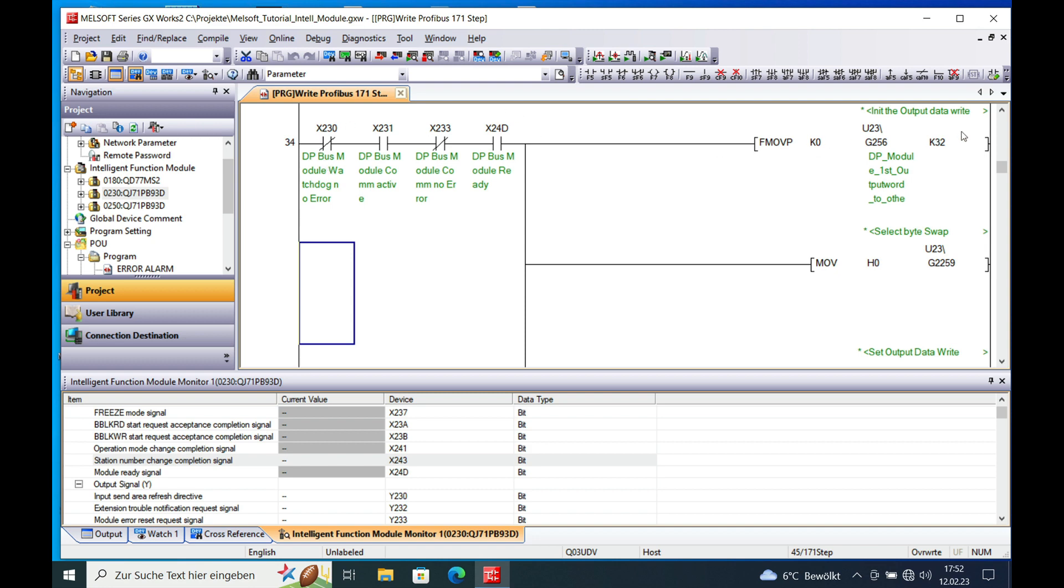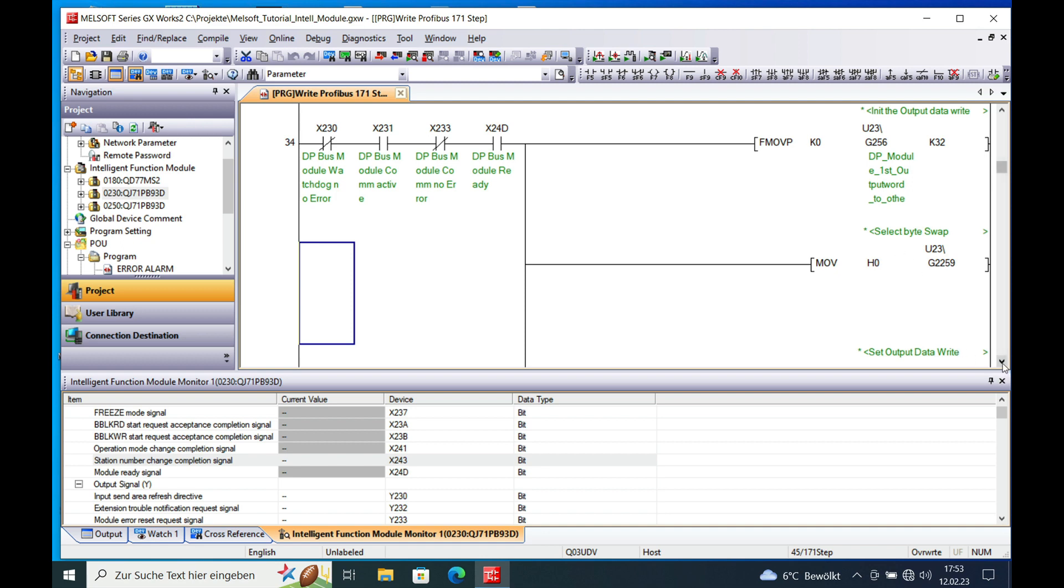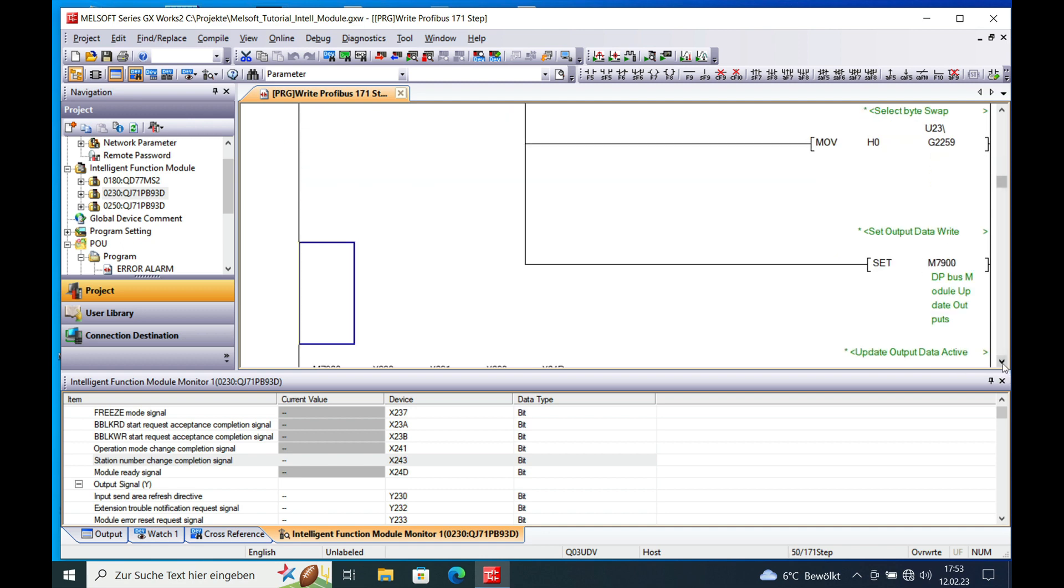First of all you initialize the output data going to the other machine and put all the zero in there. And I also provide the byte swapping function on here. Because I send this data to a Siemens PLC. And for this we have to swap the bytes inside the word.